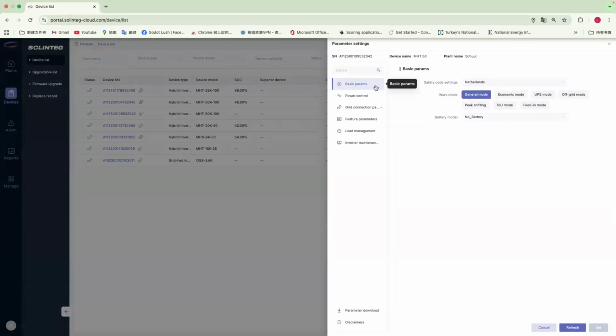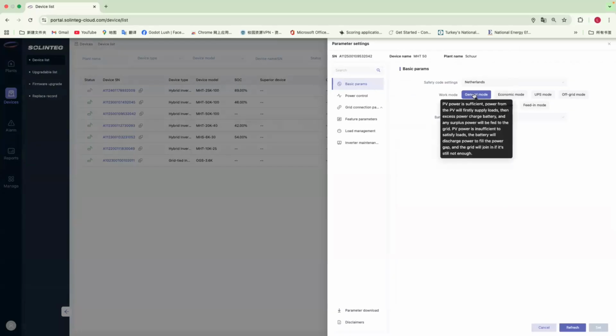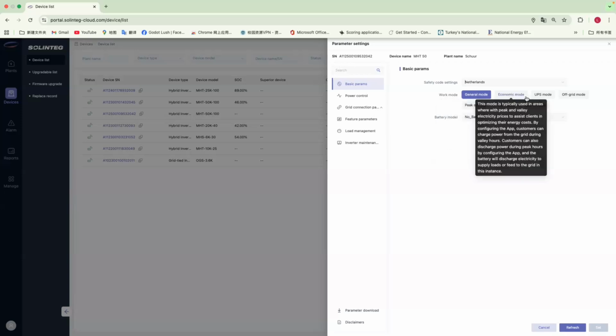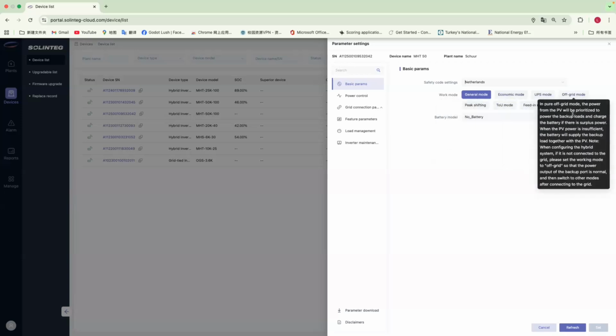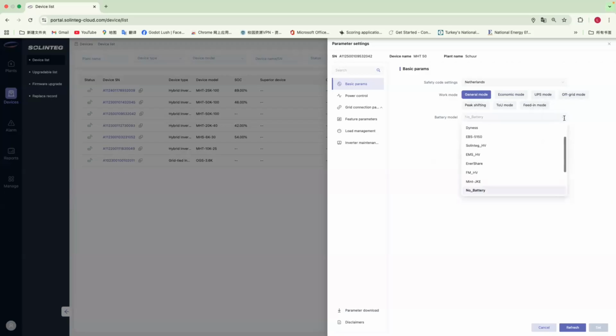First is the basic parameter settings. From here, we can choose a safety code, which is mainly related to the different regulations of different countries. Here we can change the working mode of this inverter, like choosing the general mode or the UPS mode. We have improved the design of this page by putting instructions under each mode. If we put the indicator on a working mode, it shows a basic introduction about this mode, which helps users find a working mode suitable for their requirements. And here we can choose the battery model.